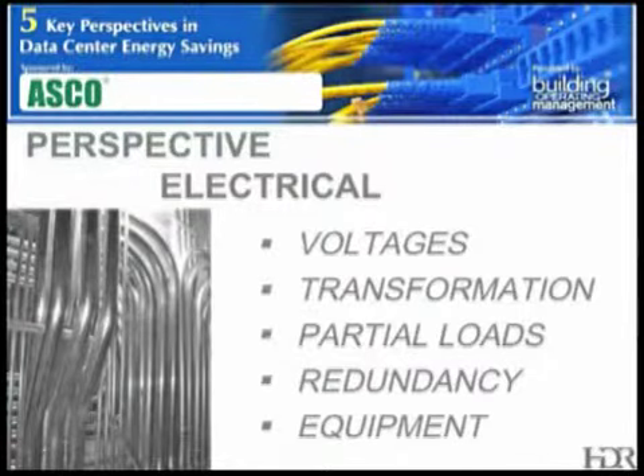Some of the other things we're seeing for distribution trends and voltage: dual inputs to the rack, whether it's a DC rack to one power supply and an unconditioned 208 or 277 volt feed to the other power supply for a dual power supply server. This places the UPS or the DC UPS at the equipment rack, and you can either operate the unconditioned power in off a UPS system in eco mode or unconditioned.